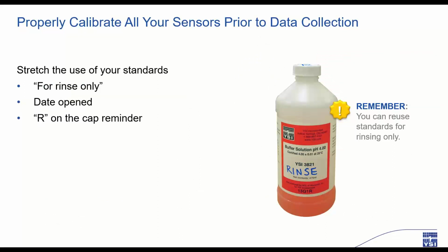In the previous slide, we stressed not using outdated or previously used standards. Error from reusing standards can come from cross-contamination of standards, debris on sensors, or even dilution from DI water used for rinses. So just make a habit of using pristine standards for your calibrations. However, one thing that you can do with your used or slightly outdated calibration standards is to reuse them for the rinsing part of the calibration process. I always save my calibration standards from today to be used during my next calibration.